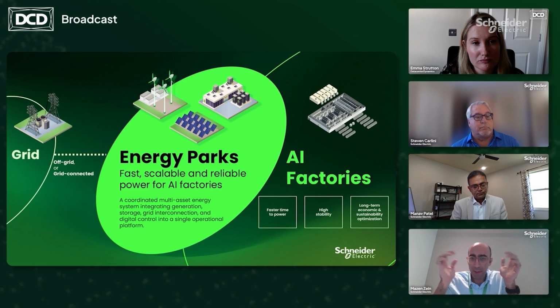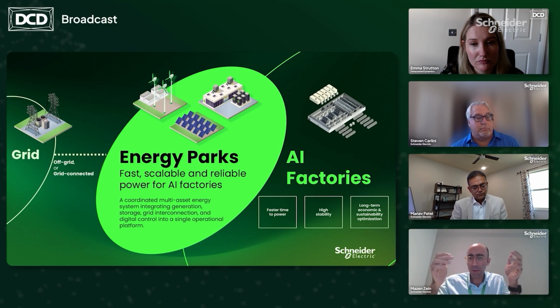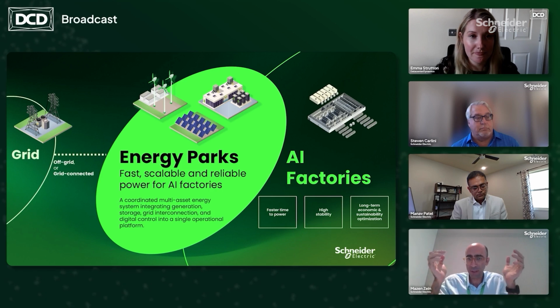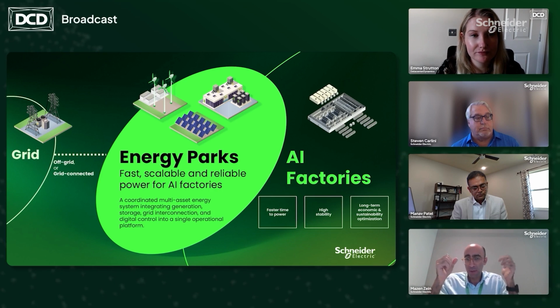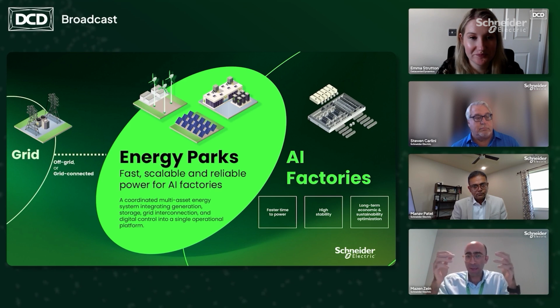Today, the scale of modern AI data centers makes the old model physically impossible. We're talking about AI campuses that can demand more than 1 gigawatt of power, comparable to the output of a nuclear reactor, which is huge. And today, no utility substation is just sitting idle with a spare gigawatt waiting to be claimed. So clearly, behind-the-meter generation is no longer a preference, and for many operators, it's the only path to getting online at all. That's mainly the difference.